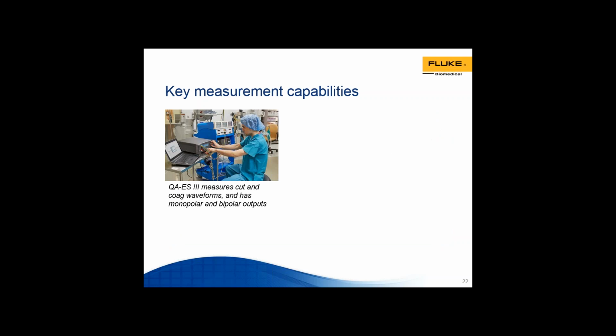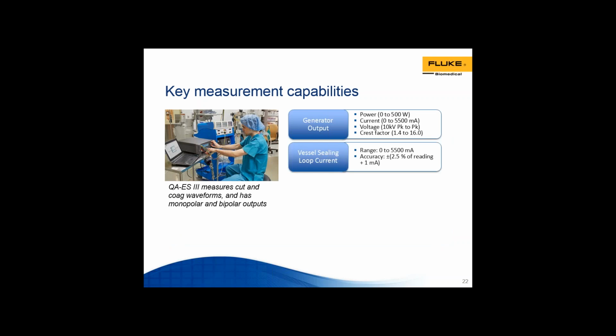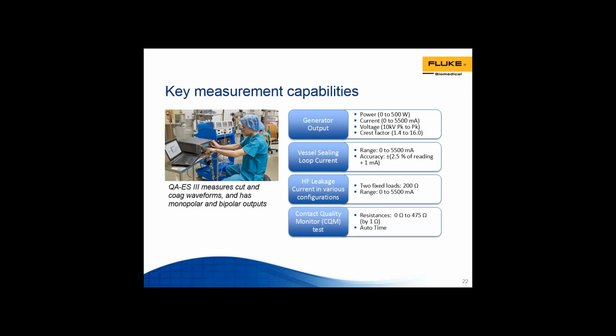A quick glance at the specification. Basically, QA-ES3 can measure cut and coag waveforms and has both monopolar and bipolar outputs. You can also see here for generator output, you can measure power, current, voltage, crest factor. Vessel sealing loop current, the range is up to 5,500 milliamps and the accuracy is 2.5% of reading plus 1 milliamp. And then you can test high frequency leakage current in various configurations, whether it's fixed loads or variable loads. And then the CQM test is actually auto. And it goes from 0 to 475 ohms and steps up by 1 ohm. And finally, power distribution. As I had described just a couple of minutes ago, you can automatically make a series of generator output measurements at various loads.